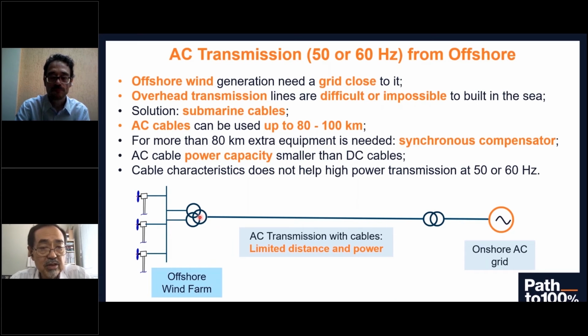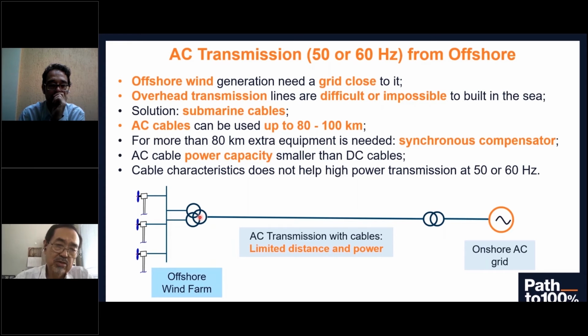The problem is that when you go offshore, in most cases, it's impossible to construct overhead transmission lines, so the solution is submarine cable. But submarine cable in AC normally has a distance limitation or power limitation. I would say it's difficult to go more than 100 kilometers, or probably more than 100 megawatts. So you have a limitation on the AC transmission.